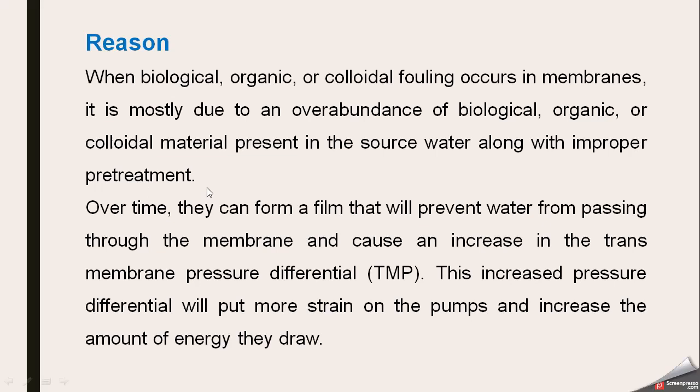Over time, they can form a film that will prevent water from passing through the membrane and result in an increase in the transmembrane pressure differential, which is known as TMP. This increased pressure differential will put more strain on the pumps which are feeding the water and increase the amount of energy they draw. So due to fouling, more energy is required to get filtered water.